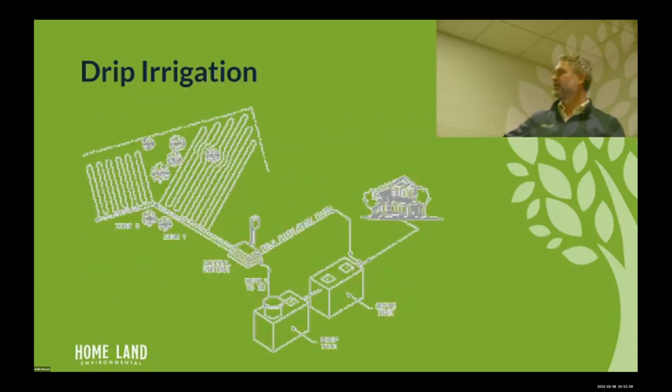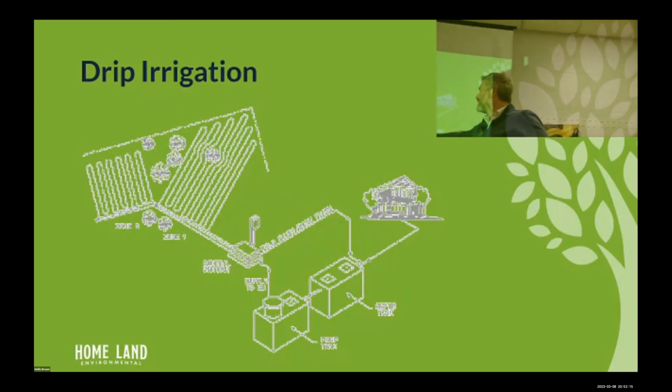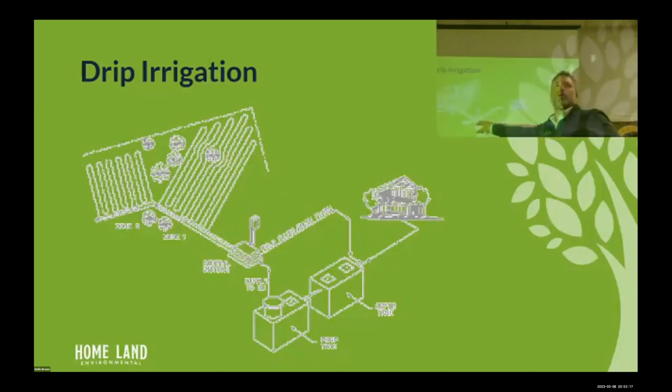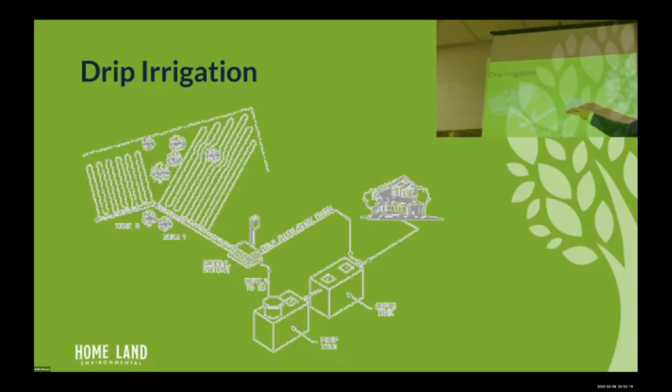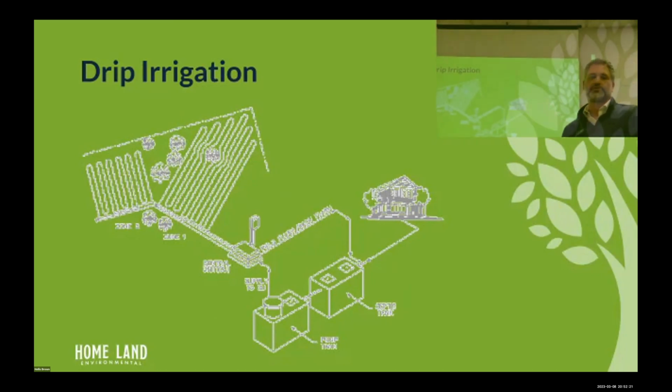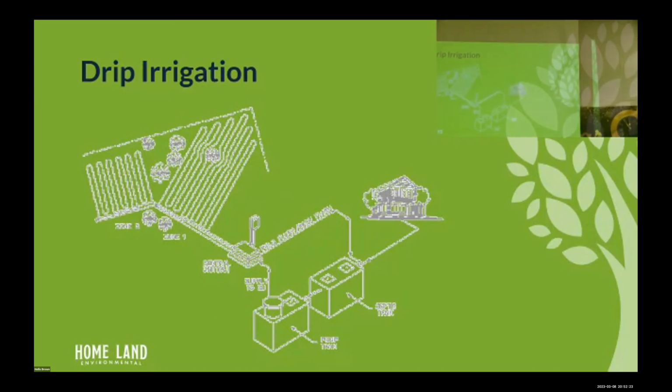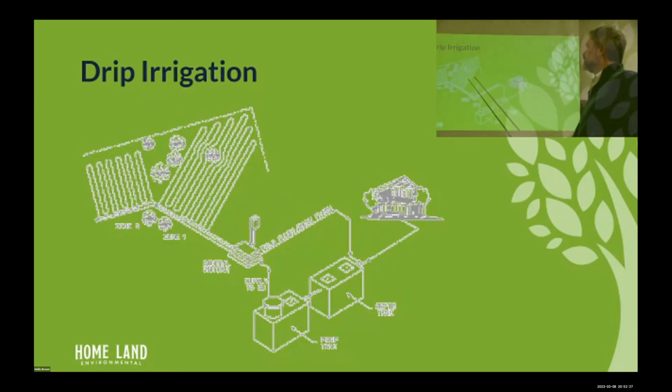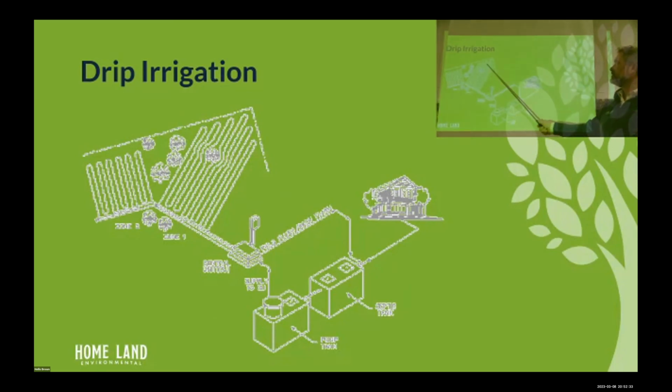And drip irrigation, I like to mention too, before we wrap up here. Septic tank, pump chamber again, then it's going to a control panel. And this control panel is controlling the zones. In every drip irrigation, just like we talked about the bull run valve, they're going to have 2 zones. This is zone 1. In this picture, this is zone 2. When this pump turns on the first time, it's going to pump to zone 1. And again, the pump is to fill up this whole lateral.